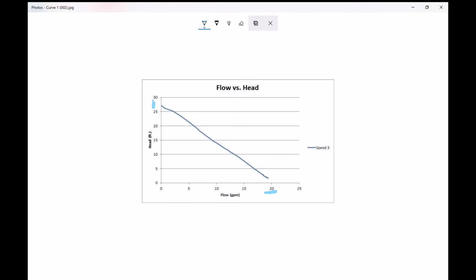So let's say, for example, in the Toronto market, Ontario, and I would assume the rest of Canada, and probably North America, a very common new application is a combi boiler satisfying the domestic load and doing a small run of in-floor heating for the basement. Well, chances are that in-floor heating could be satisfied by somewhere in this range, 20 feet of head at 5 GPM, or 10 feet of head at 10 GPM, or 15 GPM, whatever it might be.